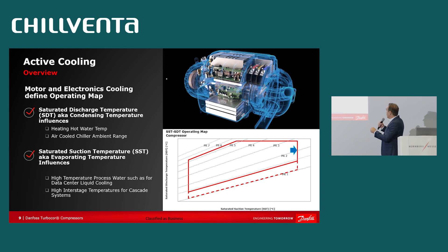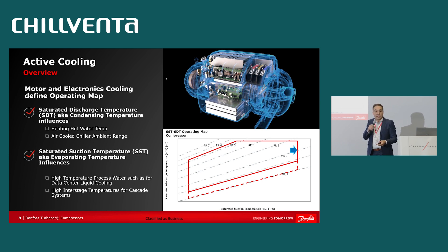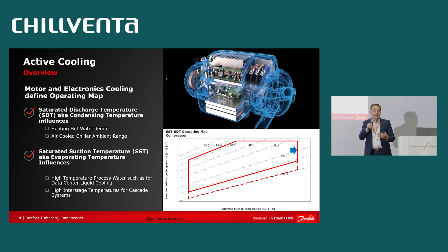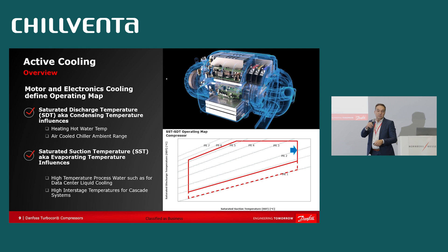The other factor is driving higher saturated suction temperatures — the evaporating temperature — which is needed for higher process water temperatures and higher chilled water temperatures, especially what's being asked for today by data centers. Turbocor today typically operates in the range of 20 to 30°C on the saturated suction temperature. To drive this above 30°C is where we need to get for liquid cooling targets. Another opportunity is complex multi-stage or compound heat pump systems, where you need to tolerate higher suction temperatures on the top-stage compressor.